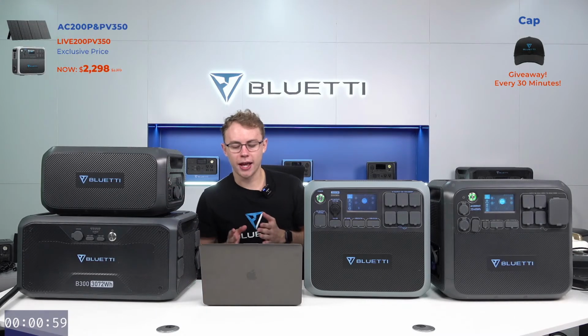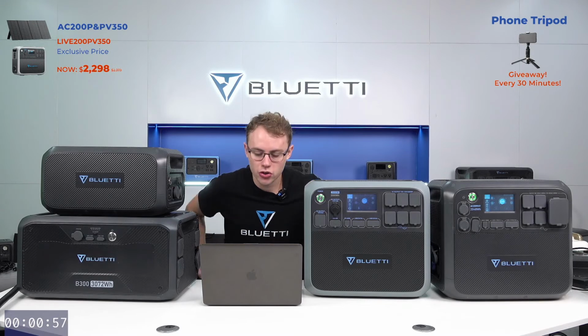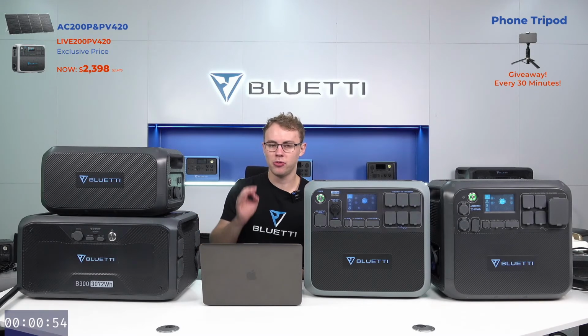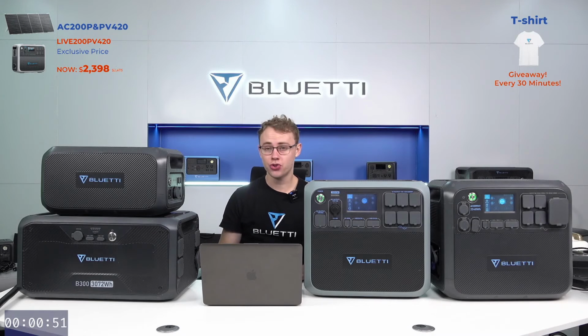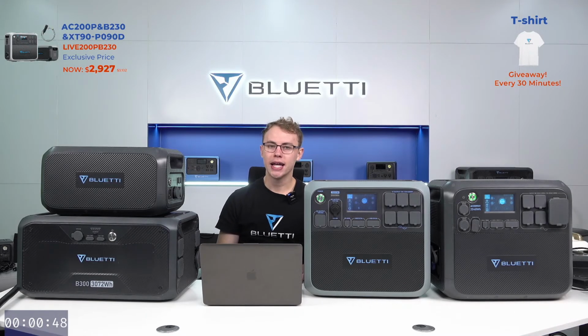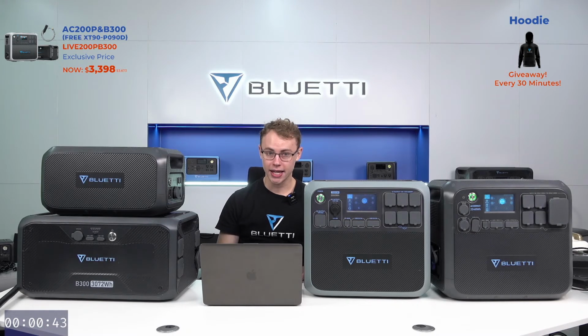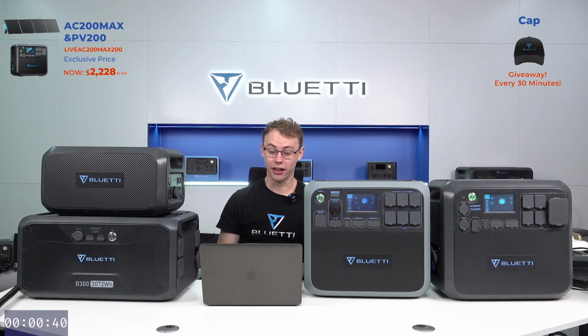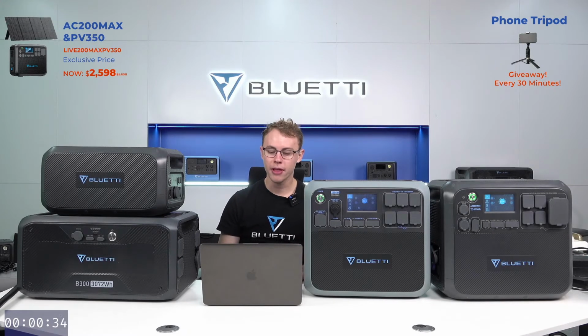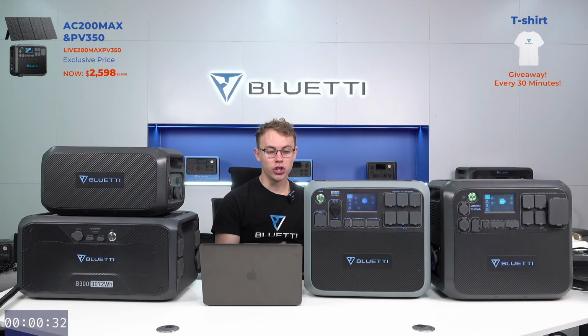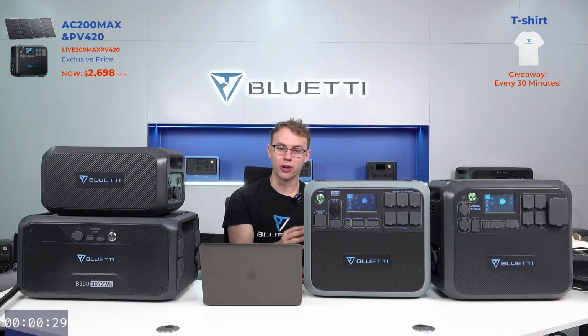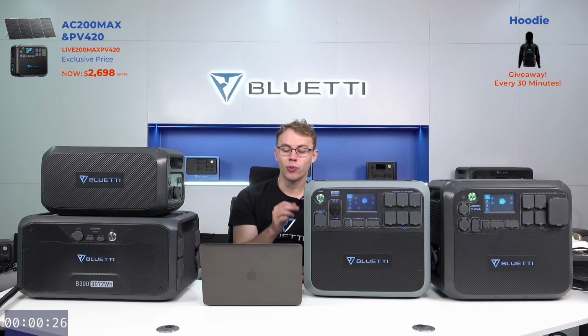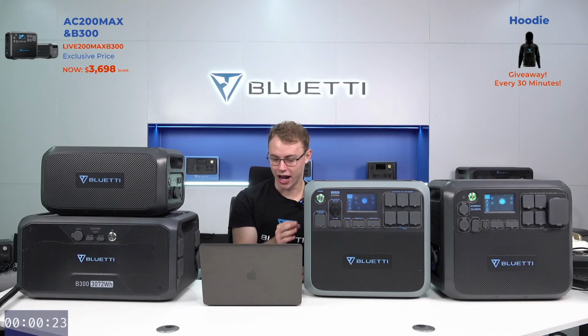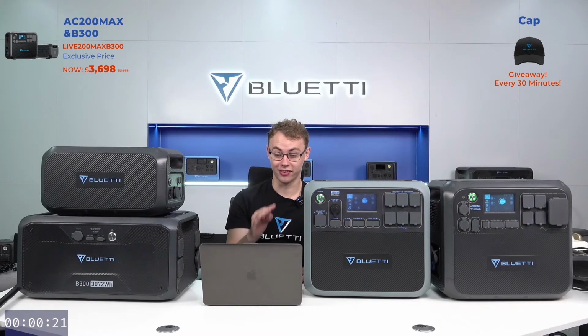Now here's an important thing. Because we use lithium iron phosphate batteries, you do want to pay attention to the temperature, specifically ambient temperature. When you discharge your unit, you don't want the ambient temperature lower than -4 degrees Fahrenheit, which equals -20 degrees Celsius—an extremely cold and uncomfortable weather. You also don't want the temperature higher than 104 degrees Fahrenheit, which equals 40 degrees Celsius, super hot.